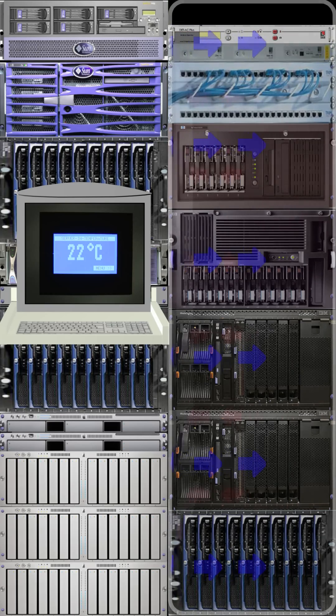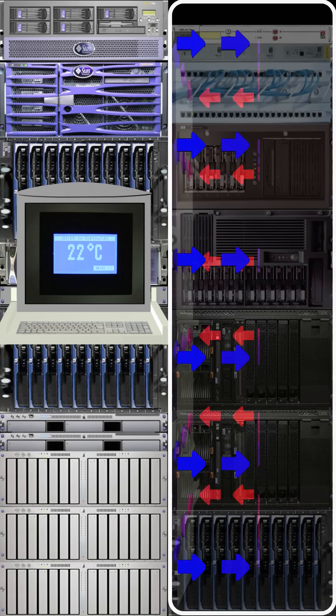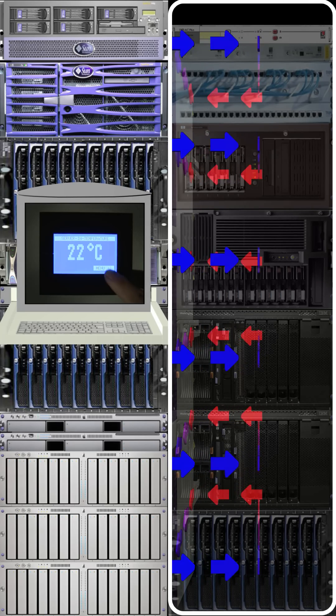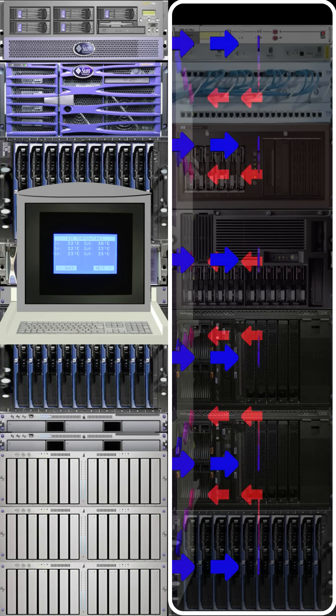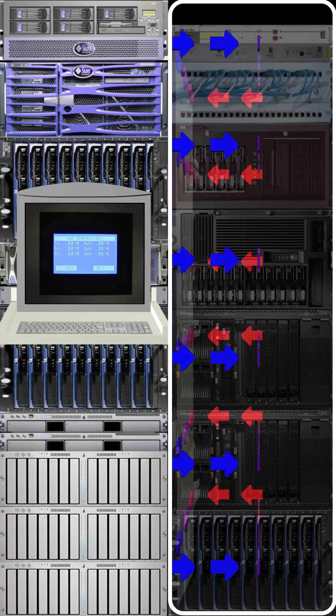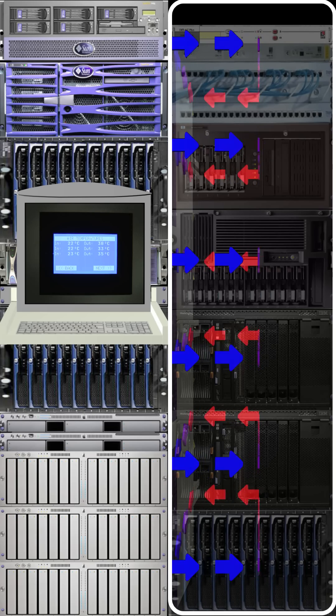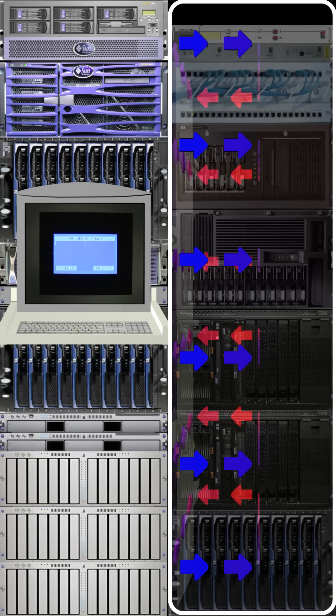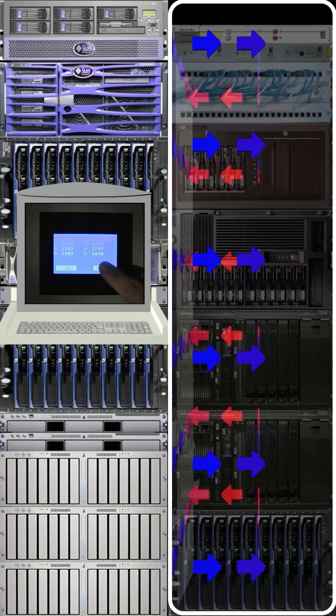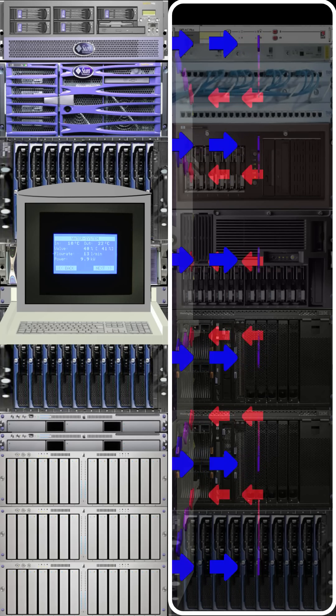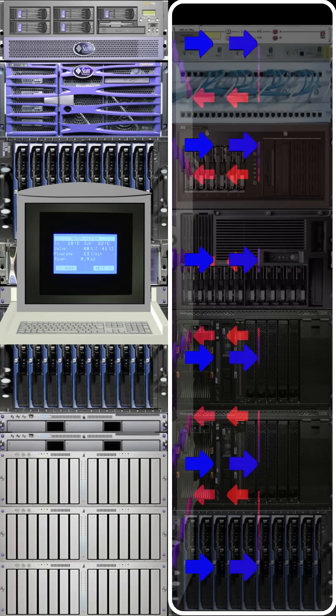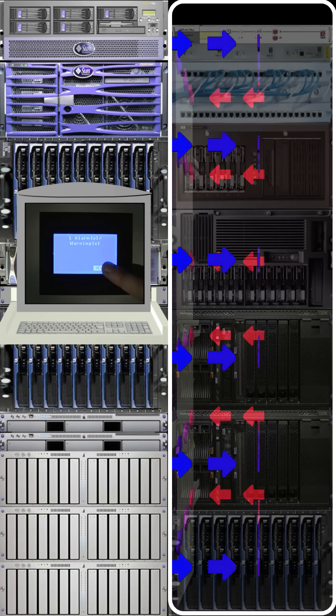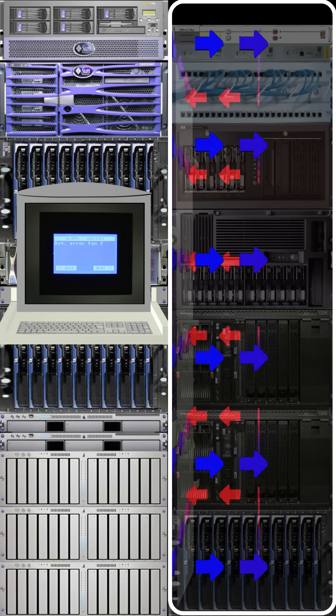A backlit touchscreen LCD permanently displays the average server inlet air temperature so you get an immediate indication of cooling. The screen can be interrogated so you can see fan rotational speeds, inlet and exhaust temperatures, water flow, inlet and outlet water temperatures, and of course any alarm activity.